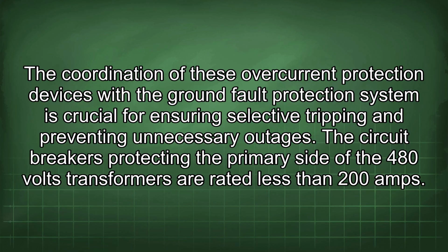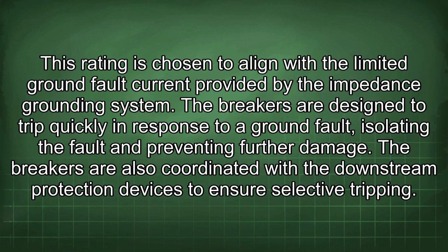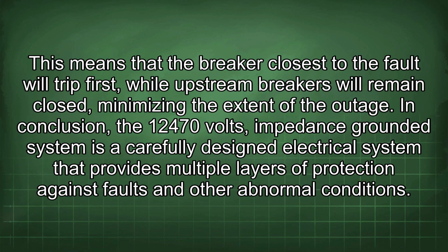The circuit breakers protecting the primary side of the 480 volts transformers are rated less than 200 amps. This rating is chosen to align with the limited ground fault current provided by the impedance grounding system. The breakers are designed to trip quickly in response to a ground fault, isolating the fault and preventing further damage. The breakers are also coordinated with the downstream protection devices to ensure selective tripping. This means that the breaker closest to the fault will trip first, while upstream breakers will remain closed, minimizing the extent of the outage.